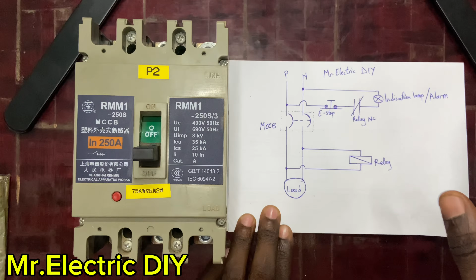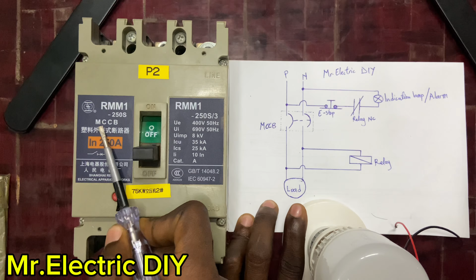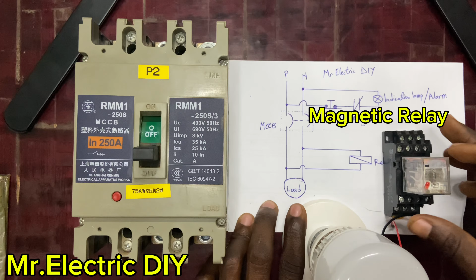I have my MCCB here, that's the breaker, molded case circuit breaker. I have my load here, this is the load, and this is the MCCB. I have it written here, MCCB. And over here is the relay. This relay here is what is going to help me do the trip, because I need the normally closed contacts on the relay to do this trip indication here. So I have to connect this relay.